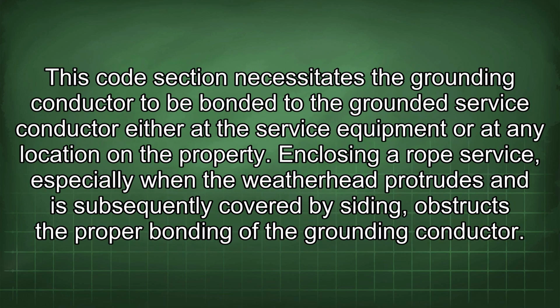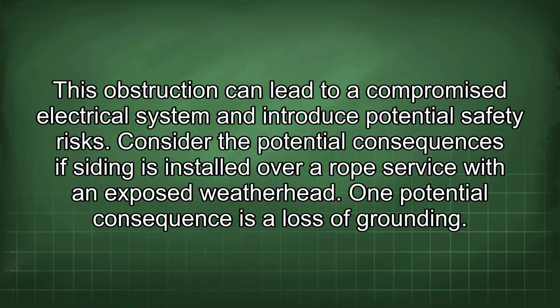This code section necessitates the grounding conductor to be bonded to the grounded service conductor either at the service equipment or at any location on the property. Enclosing a rope service, especially when the weatherhead protrudes and is subsequently covered by siding, obstructs the proper bonding of the grounding conductor. This obstruction can lead to a compromised electrical system and introduce potential safety risks.